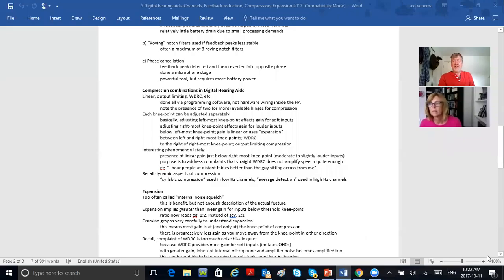Back to the question: does fitting method affect feedback? Well, if the fitting method is suggesting a lot of high-frequency output, you're flirting with feedback, because high-frequency output and peaks in it are what cause feedback. When you use feedback reduction to get rid of the peaks, be careful — you'll throw out too much high-frequency gain, which you want. There's always a bit of a tussle there.